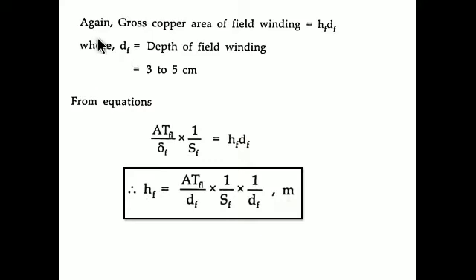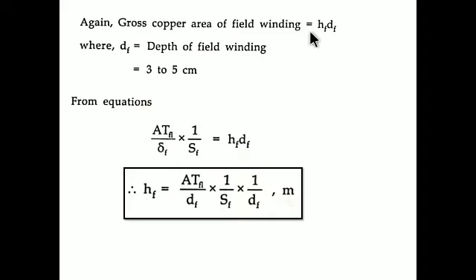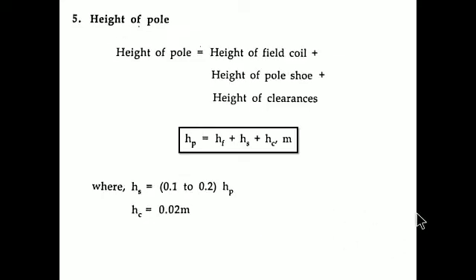There is another method to find the gross copper area: it equals the height of the field coil hf multiplied by the depth of the field. The depth of the field is approximately 3 to 5 centimeters. By equating these two expressions for gross copper area, we can solve for hf — the height of the field coil. Note that ATfl used here is the full load field MMF calculated in the previous procedure.